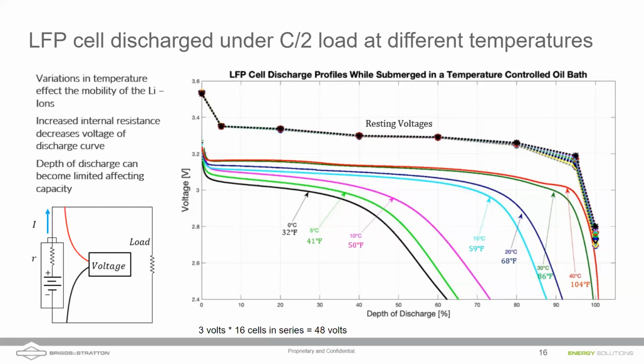If you just stopped the system from discharging and looked at the resting voltage, you could check one of our charts and say, I've got 52% left in the battery. Some inverters are better than others at estimating how much energy is left—they'll say it's at a 30% state of charge, and you can trust that number. But some older equipment is worse at seeing how much energy remains in the batteries, so if you have questions, call tech support.